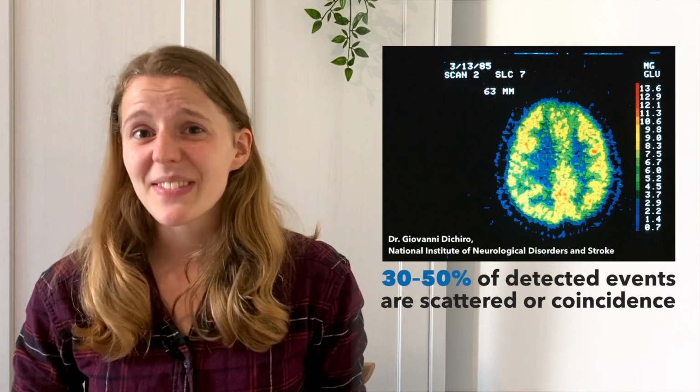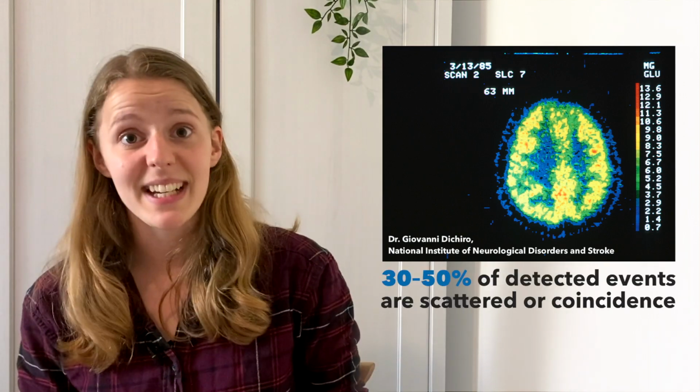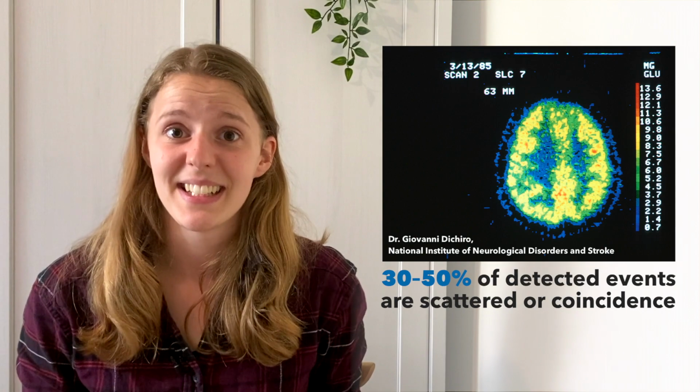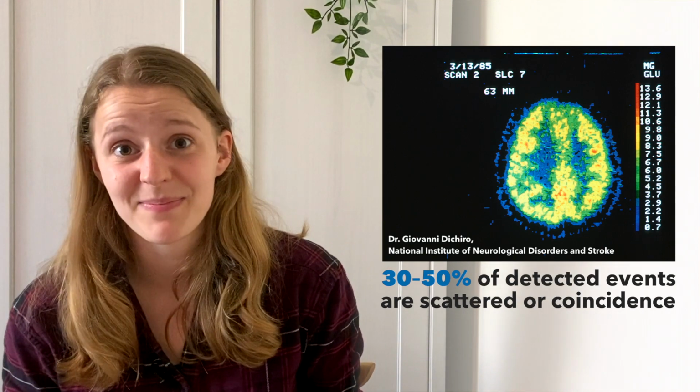Unfortunately, for a full-body PET scan, 30 to 50% of all the events we detect can be these scattered events, and that is a huge fraction. So as a result, PET scans tend to be noisy with bad spatial resolution. It's hard to see a lot of detail.